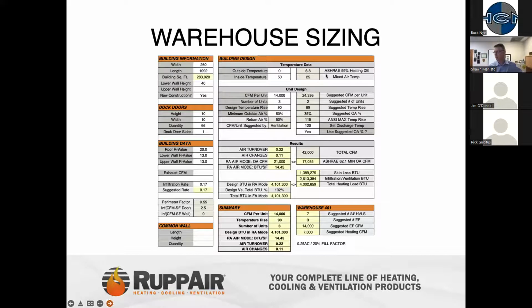The software is also going to give you suggestions based on what ASHRAE is going to state, because up on top we aren't showing this, but you basically can set your city and state. From there, it's going to give you design criteria you recommend. Now, what you're going to see on the left-hand side here doesn't quite match what we have on the right. In this case, this client actually wanted to have 3 units rather than 2, because they wanted to have 3 zones of operation in this building.